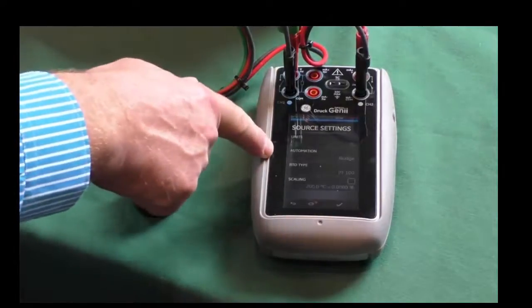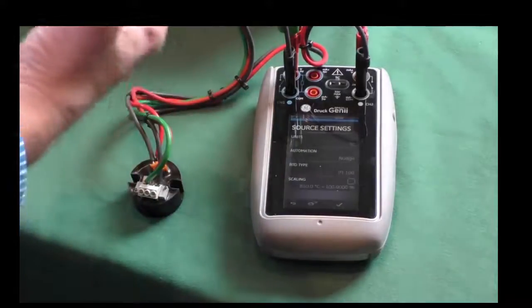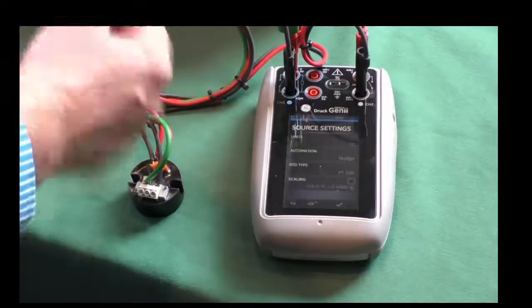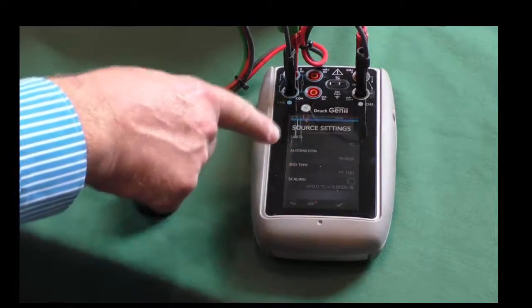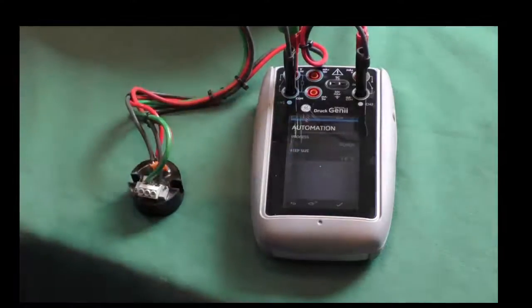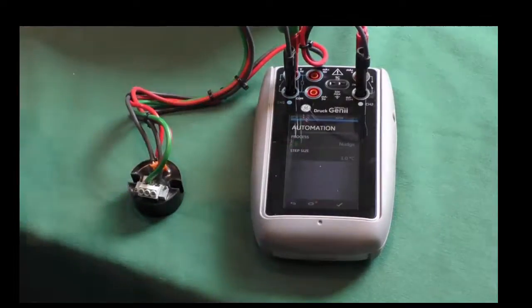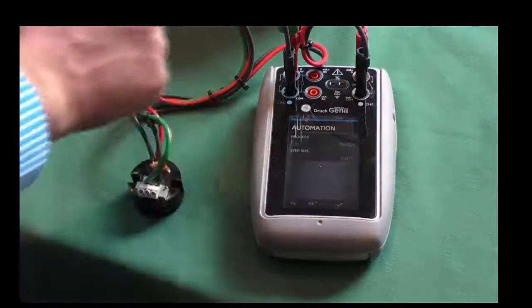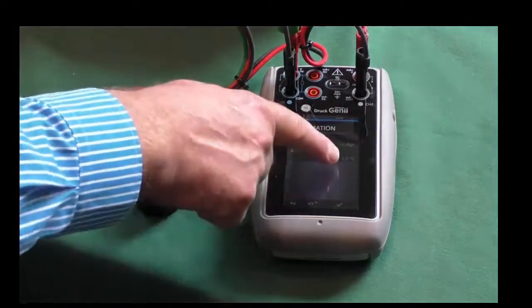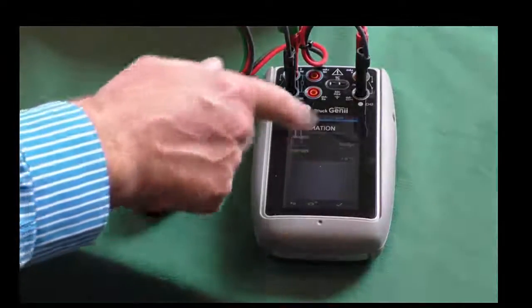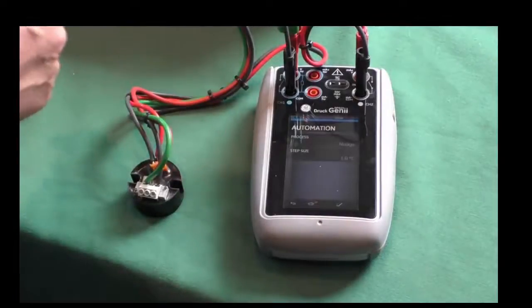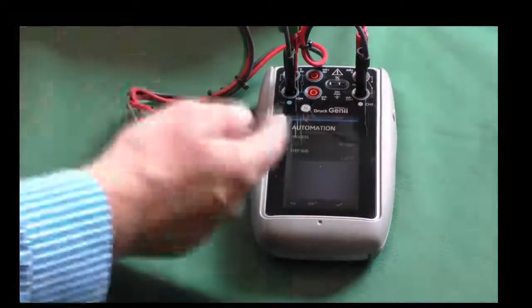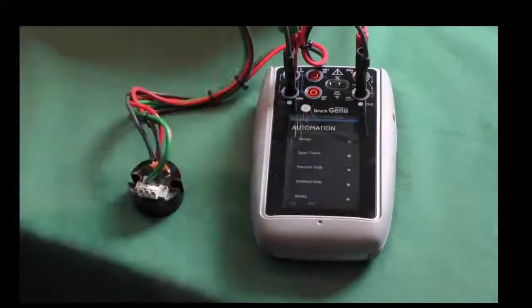But what I'm interested in here is I can obviously change the RTD type. We have 12, actually 14 different RTD types in there. This one is PT100, which is already set up. So I can go into the automation side of this. And on the automation at the moment, I've got nudge value. So I can nudge this up and also adjust the step size of that nudge. Currently, it's set at 1 degree C. So every time I press the arrow, it'll go up or down by 1 degree C. And obviously, I can change that to any value I wish I want to. But to make it easier, let's do a process here.